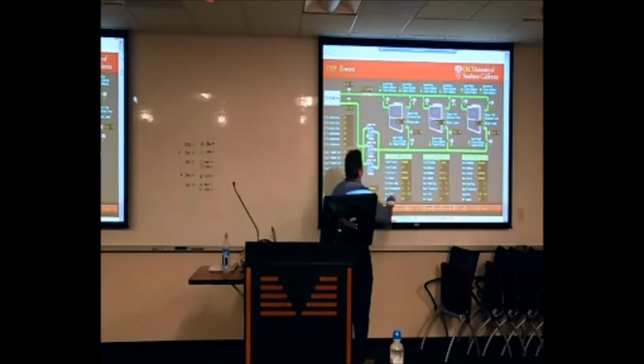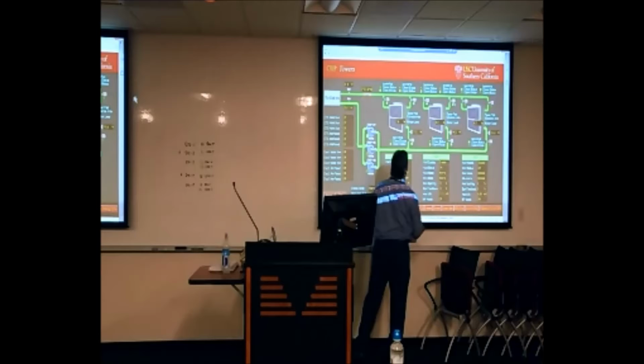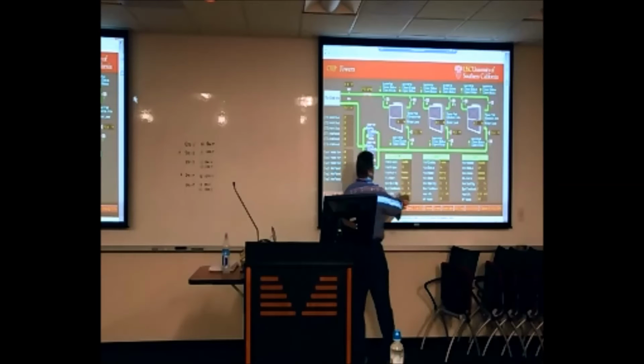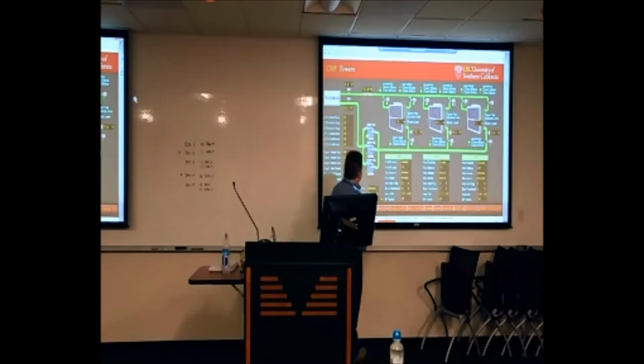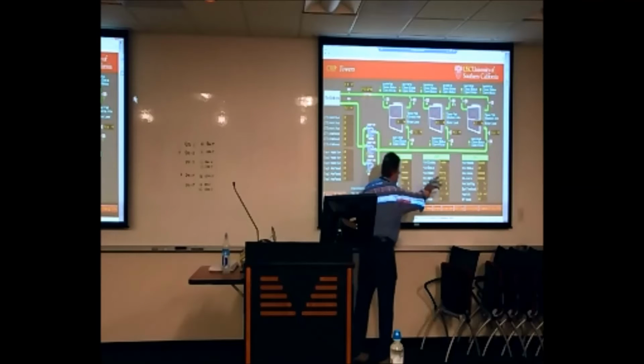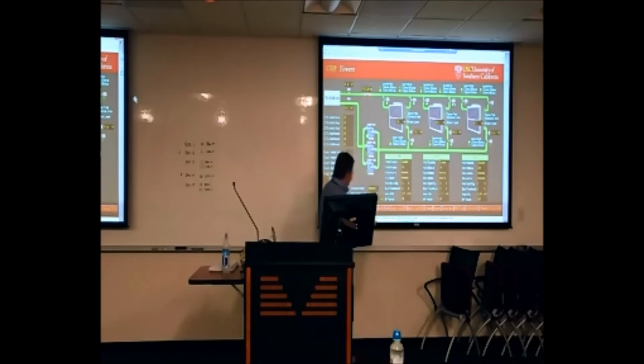Alrighty, each tower has a single fan associated with it, and with that fan is a single variable speed drive operating each one of the fans. And for each drive, we have the drive enable command, variable speed drive status, variable speed drive alarm, vibration alarm, the VSD speed signal, the current signal going out to control the drive, and then the feedback signal coming back from the drive, verifying that we're at that speed. And then we also monitor the KW for each one of these drives, and we add those up, and I'll explain where they come into the sequence.